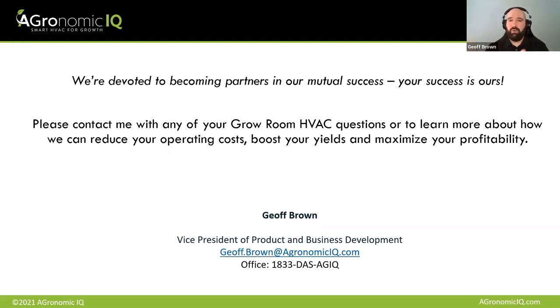I'd argue the most appropriate place is drying rooms. Desiccant systems are capable of very accurate dehumidification control, applying a consistent dehumidification amount, pounds per hour or delta grains, to an airstream across a wide range of temperatures. If you wanted to dry at 60 degrees Fahrenheit and 40% relative humidity, you have a very low dew point, lower than DX or any direct expansion dehumidifier can achieve.